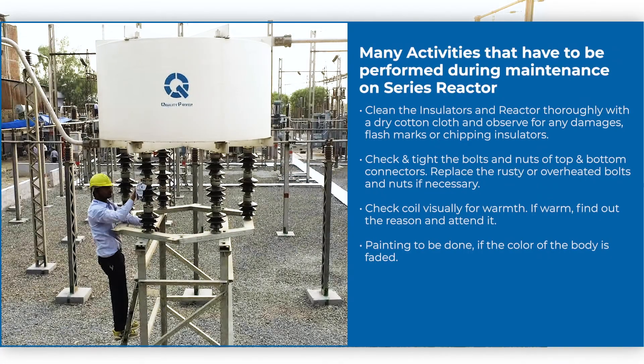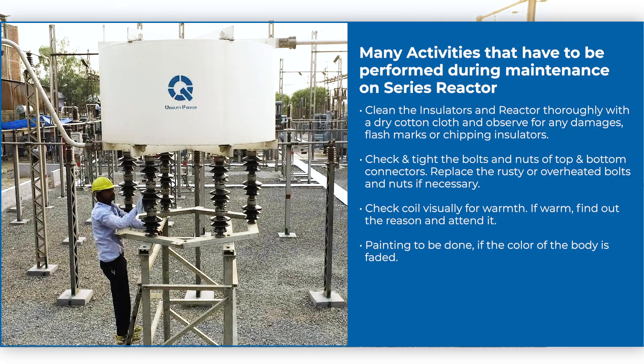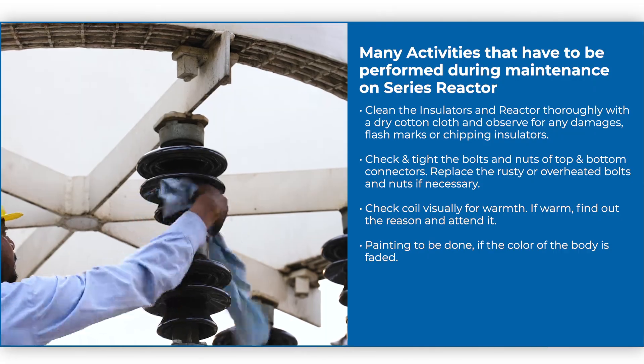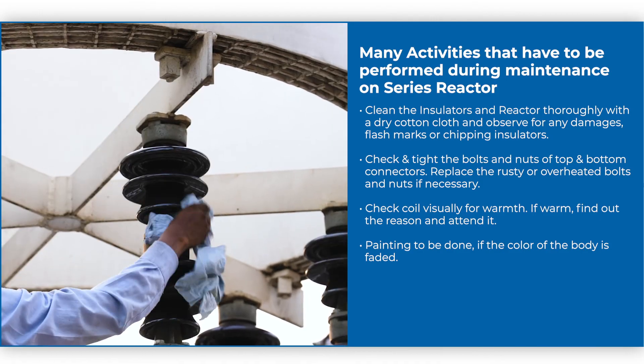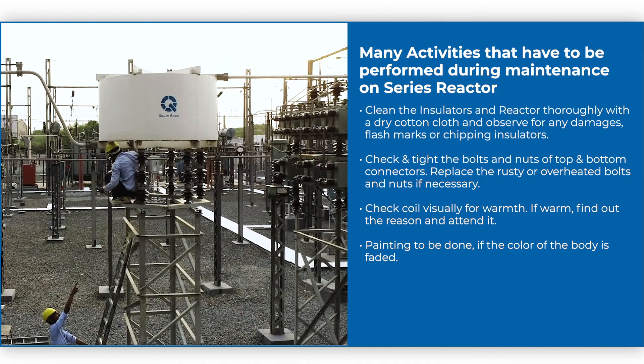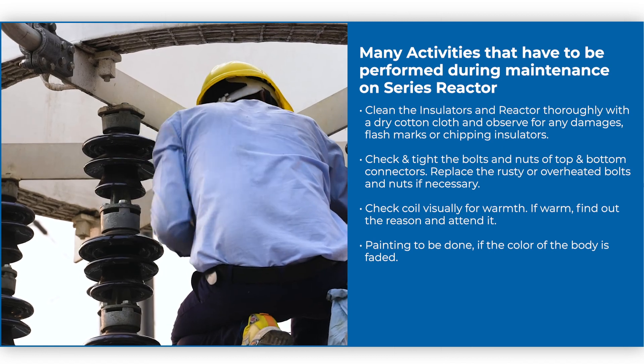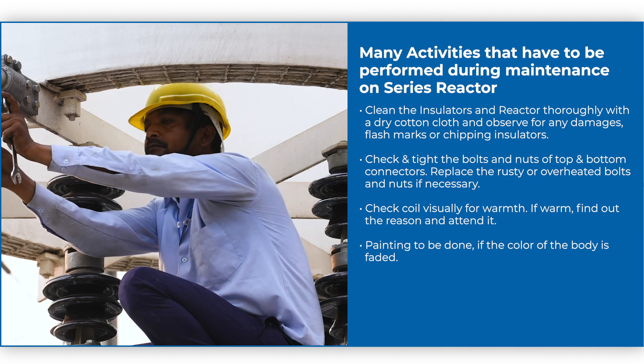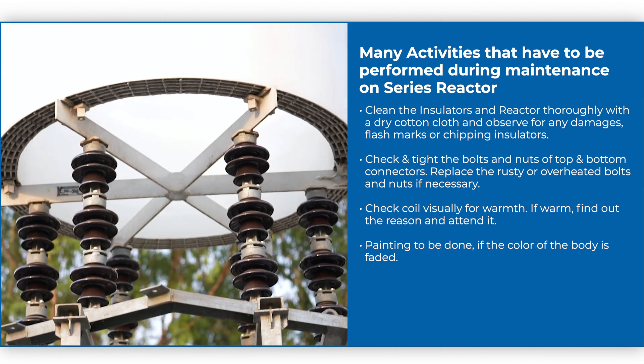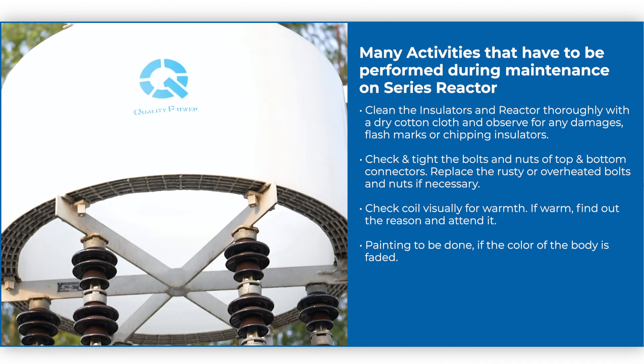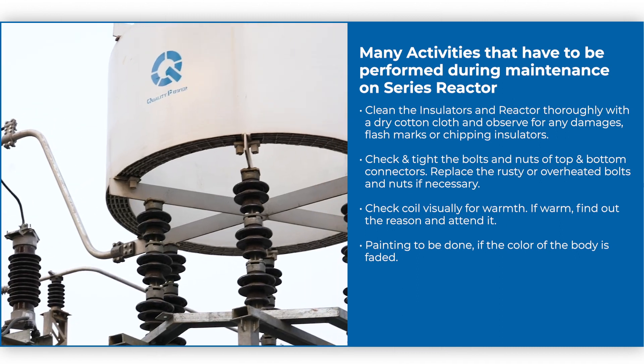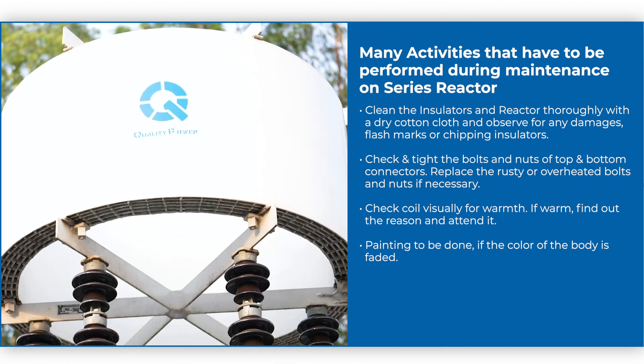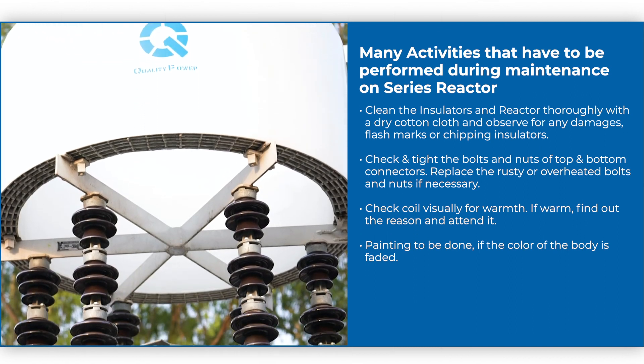Maintenance of series reactor: clean the insulators and reactor thoroughly with a dry cotton cloth and observe for any damages, flash marks, or chipping of insulators. Check and tighten the bolts and nuts of top and bottom connectors, replacing rusty or overheated bolts and nuts if necessary. Check visually for warmth; if warm, find out the reason and attend to it. Painting is to be done if the color of the body is faded.